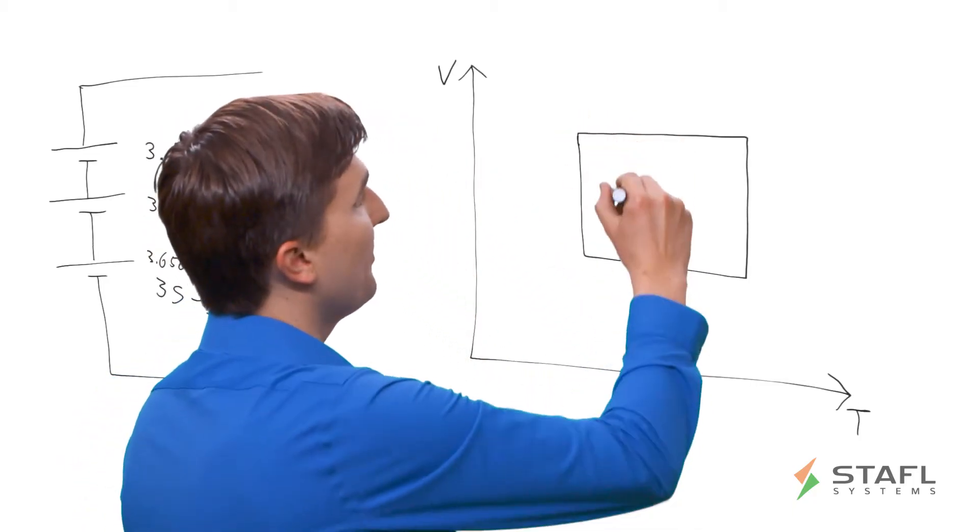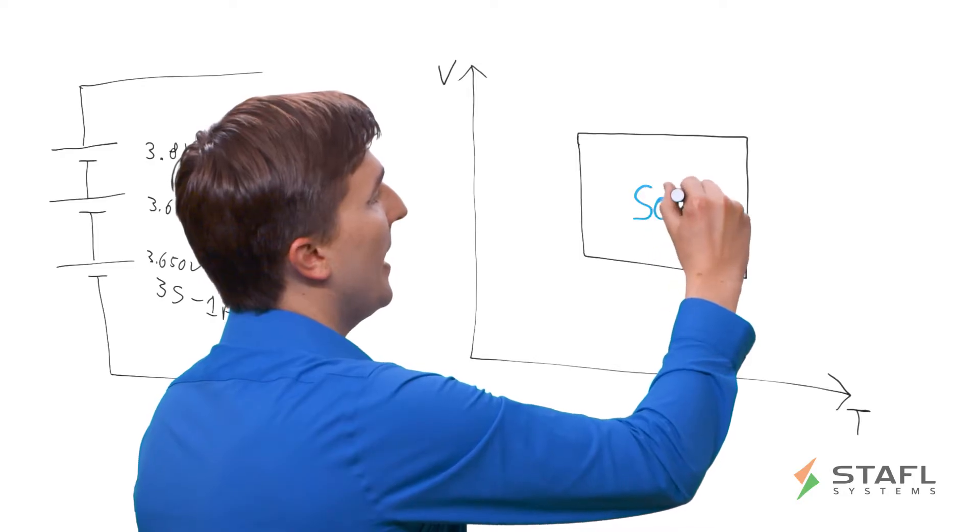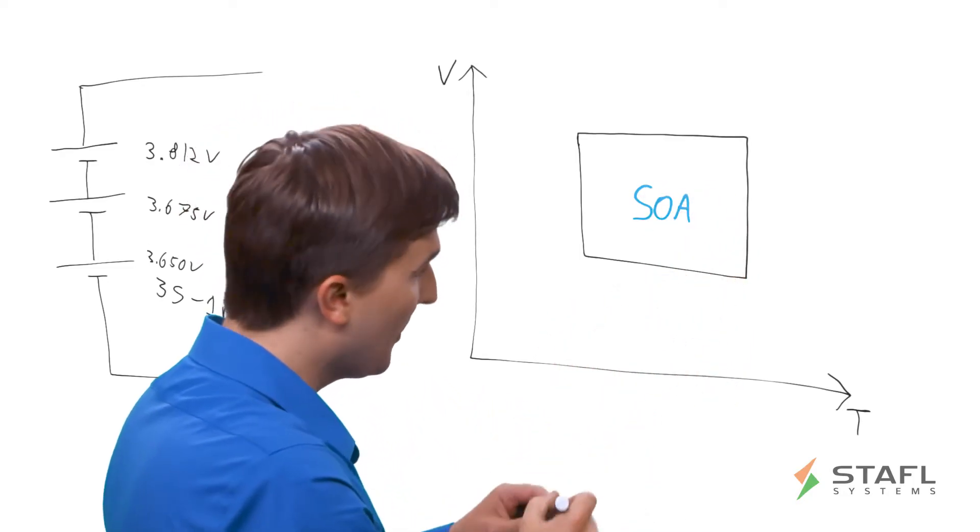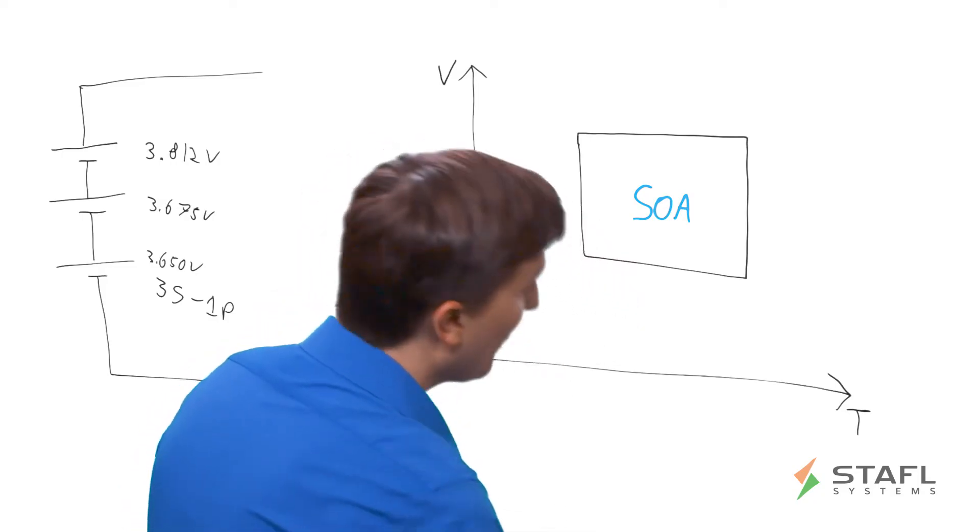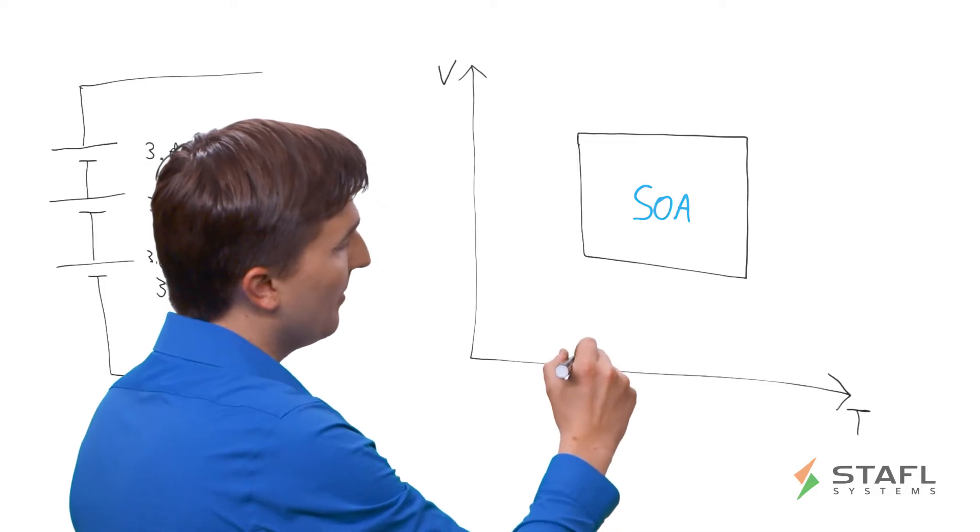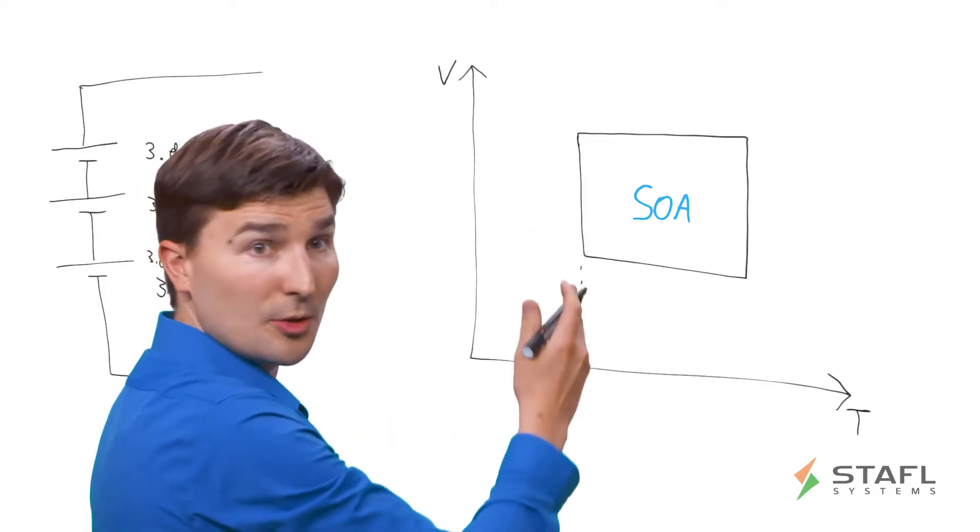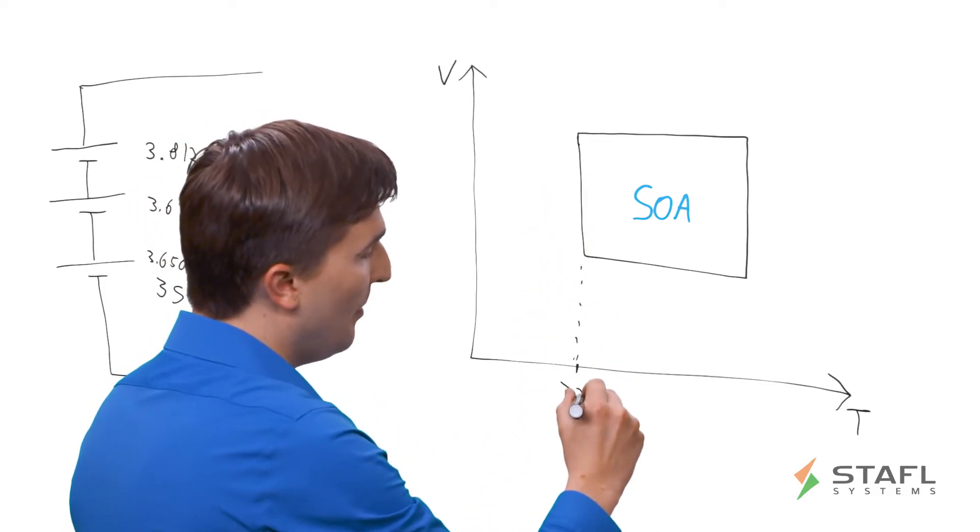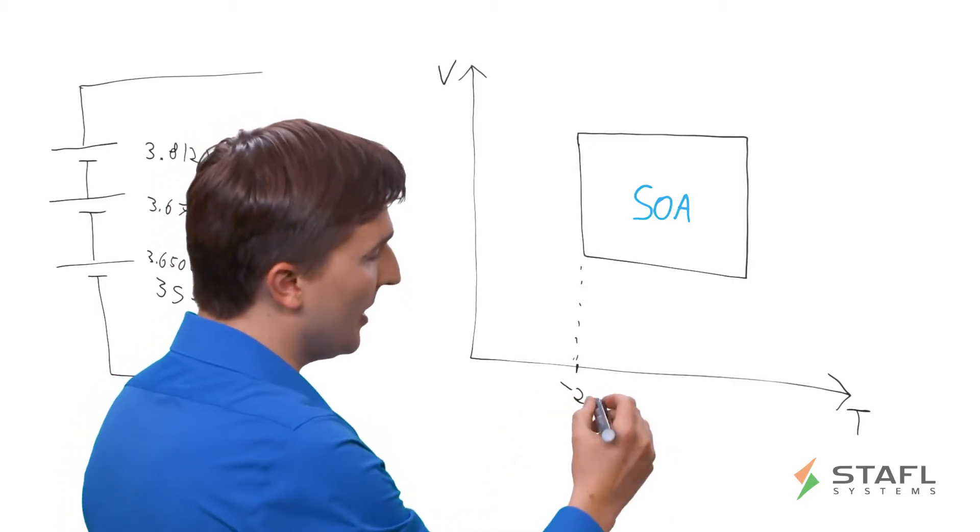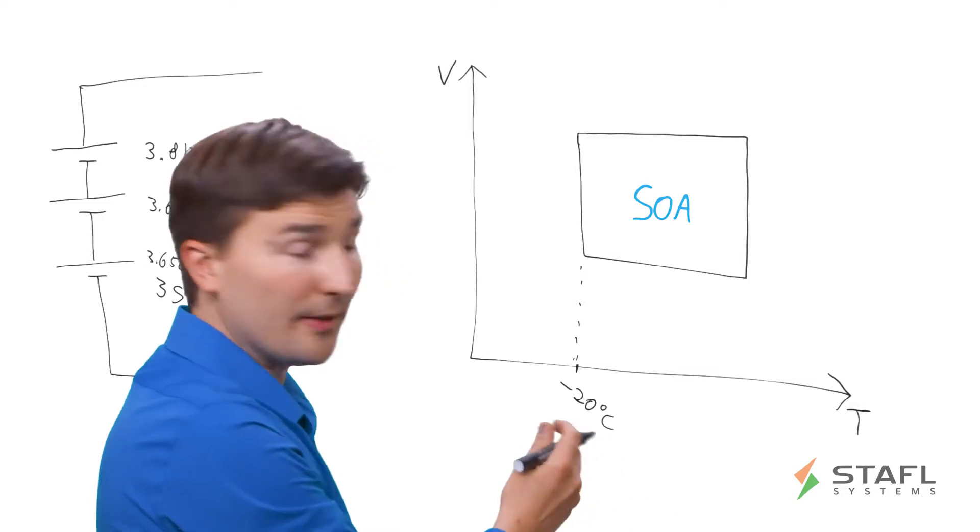So this region is the SOA, or safe operating area of the lithium-ion cells. And how do you define that? Well, down on the x-axis, this point here, which corresponds to this side of the square, is the minimum safe temperature that you can operate the cells at. For example, some cells will have a minimum temperature of negative 20 degrees C.